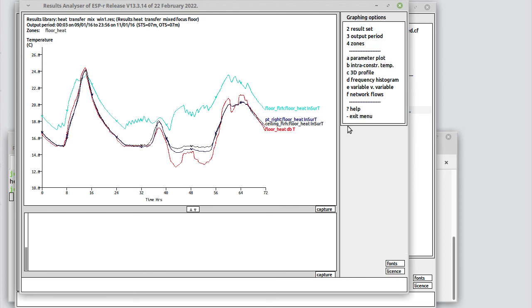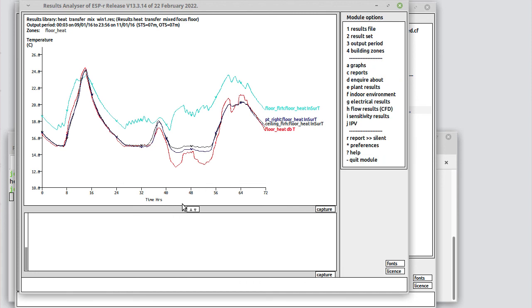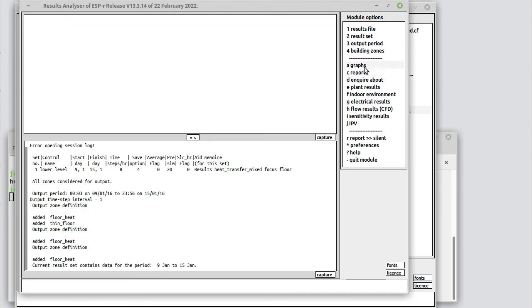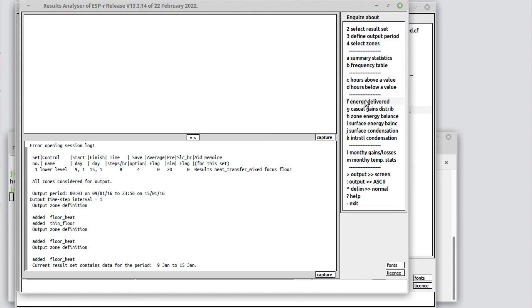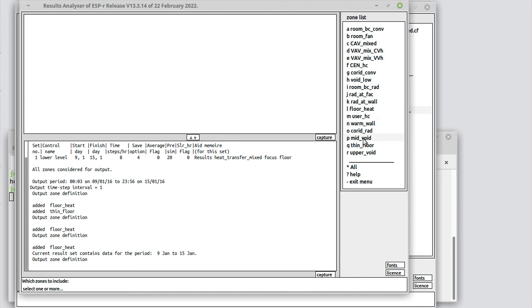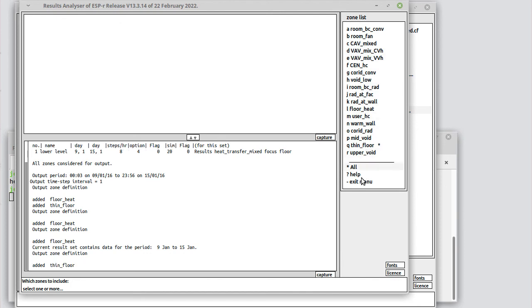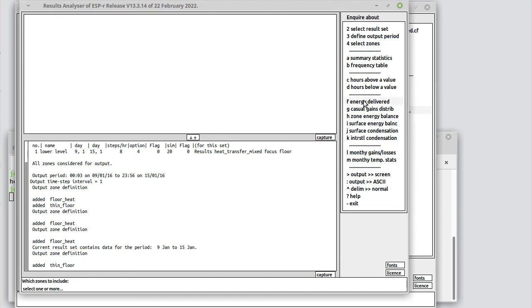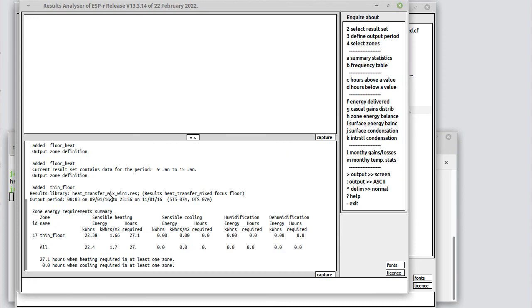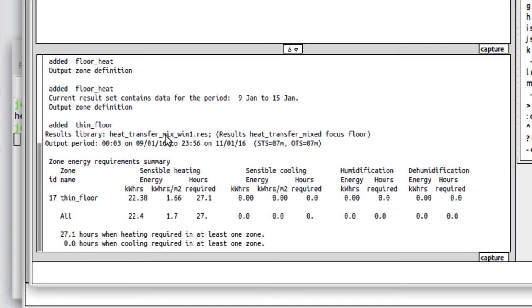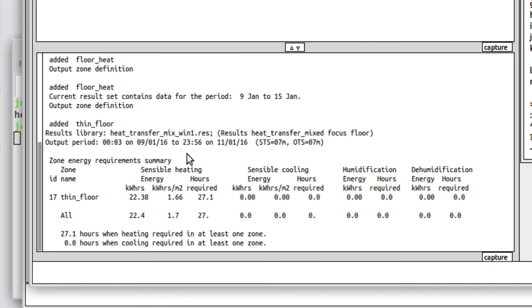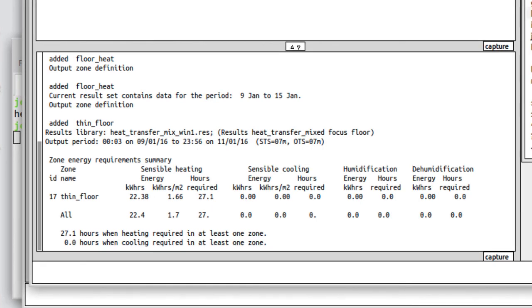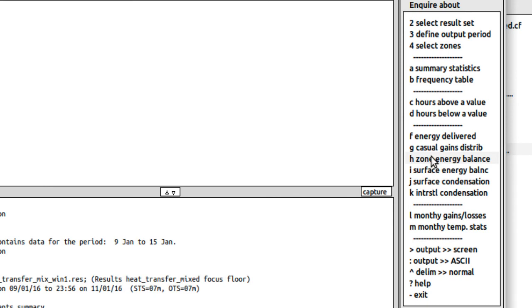What other kinds of things might we look at? If we go in to inquire about what kind of energy is delivered, we want to go and select the thin floor because that's where the heat is being injected. Over those 9th, 10th and 11th, we've got 22.38 kilowatt hours into the thin floor, which is equivalent to 1.66 kilowatt hour per square meter. It's needed for 27 hours.